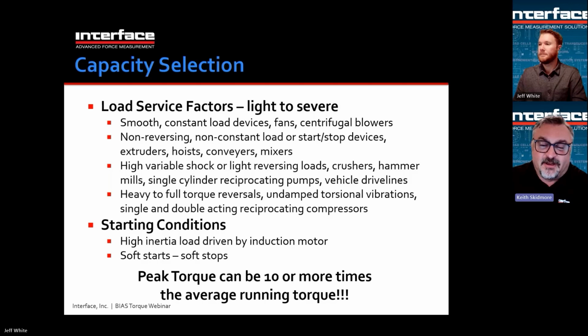And then worst case would be heavy to full torque reversals and undamped torsional vibrations. At certain RPMs and certain stiffnesses in the driveline, you can get vibrations. If those are undamped, they can be very severe, which creates large torsionals, things like that. So imagine you have a very hard drive service, say a single cylinder diesel, and you had a very difficult load like a hammer mill or a grinder. You would have to multiply by a factor of maybe 5. So if it's 100 Newton meters average running torque, you might need a 500 Newton meter sensor.